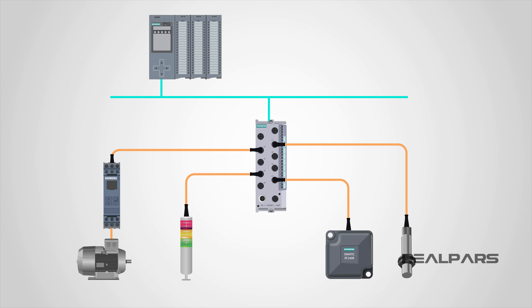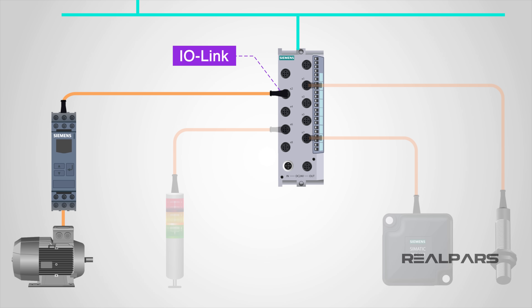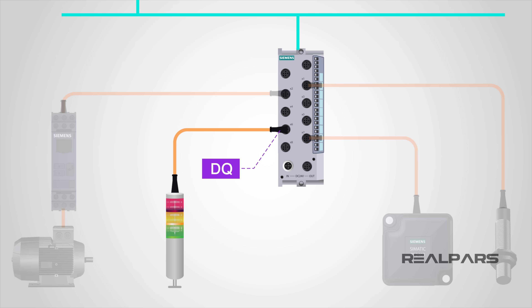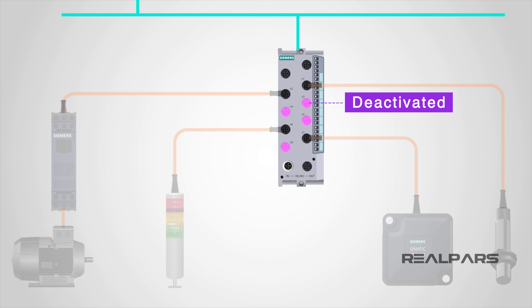The IO-Link protocol allows an IO-Link port to be operated in one of four different operating modes. The first mode is the IO-Link mode, meaning the port is used for IO-Link communication. The second mode is the DI mode, meaning the port acts in the same way as a digital input device. The third mode is the DQ mode, meaning the port acts in the same way as a digital output device. The fourth mode is deactivated, meaning the port is not assigned to any other modes and is reserved for when the port is unused.